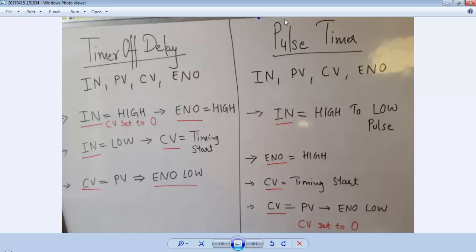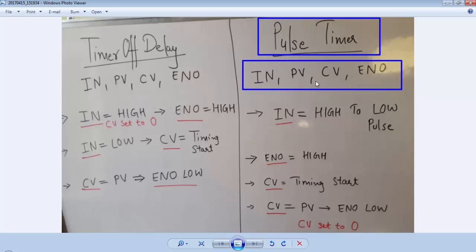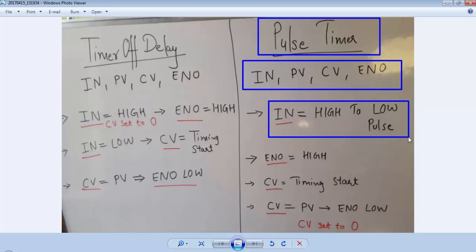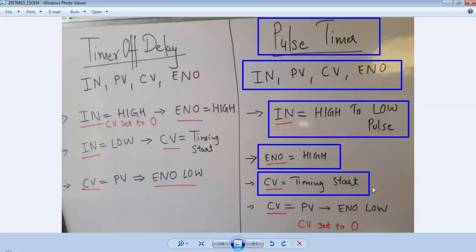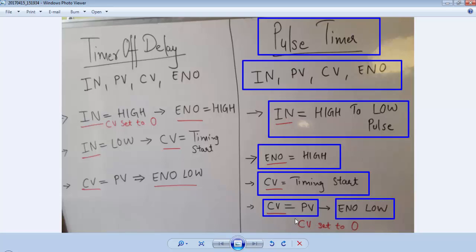For a pulse timer we have same four variables: input, preset value, current value and enable output. But the behavior is different. We have to provide a high to low pulse on IN pin of the timer, then the timer will activate the ENO pin and at the same time the CV will start its timing and it will go up to the PV value. Whenever the CV value is equal to PV value the ENO becomes low, means output becomes low, and at the same time the CV will be reset to zero so that we can again provide a pulse to activate the timer.